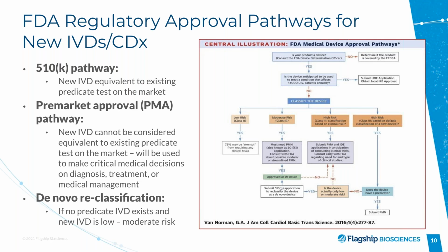And there is another pathway that is called de novo reclassification, where there is no predicate IVD that exists on the market. However, the new IVD or CDx is of low risk or moderate risk, in which case, again, no comprehensive clinical evaluations will be required.